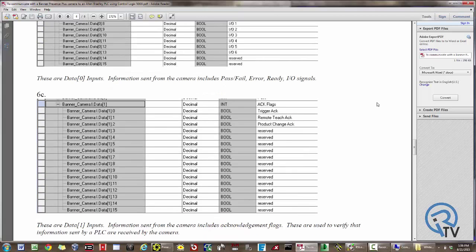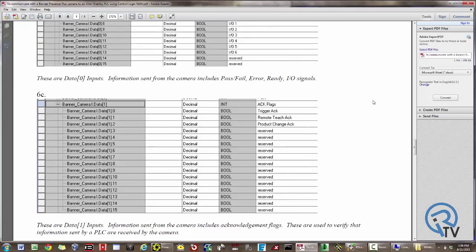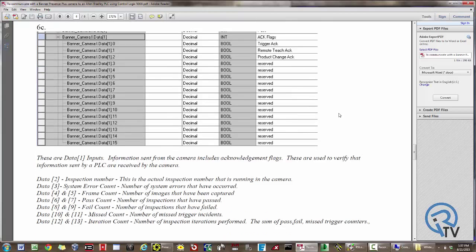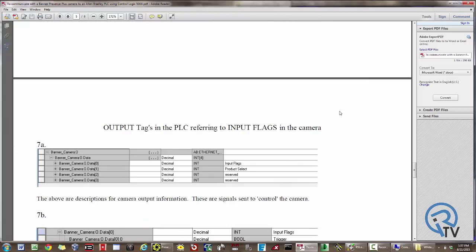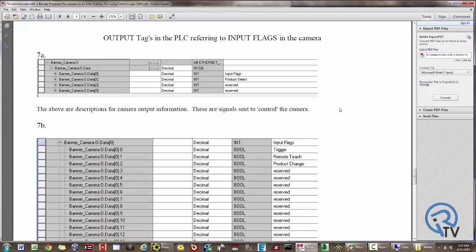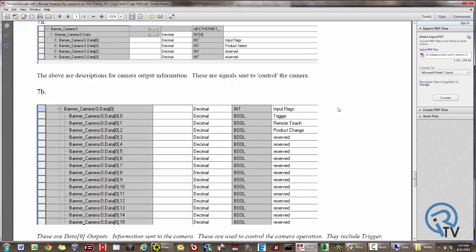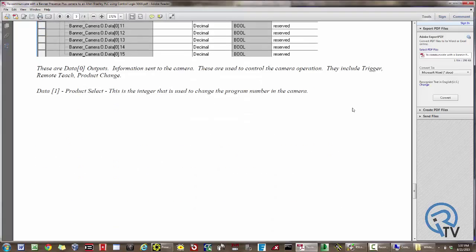My acknowledgement flags, which are really useful to make sure your inputs go into the camera correctly — I get acknowledgement that the camera received the trigger, remote teach, as well as product change. On the output tags to the PLC, here's where I'm going to trigger the camera, give it a remote teach, or issue a product change.